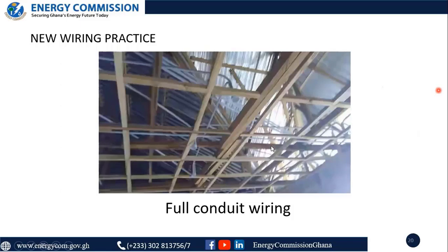When you put a ceiling there and a cable is running bare on it, normally they secure the cables with nails. With time, when you run the cable round the nail just to let the cable be firm, you're causing something we call inductance, because the cable is also a conductor. Once the cable is not meant to act as an inductor, you cause heating in the cable at that point where you've rounded it over the nail.